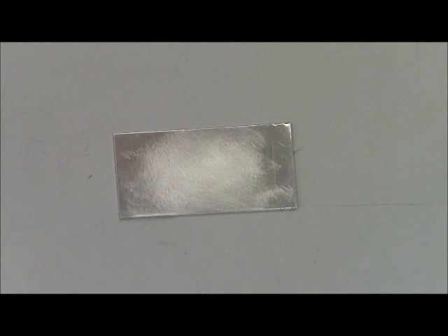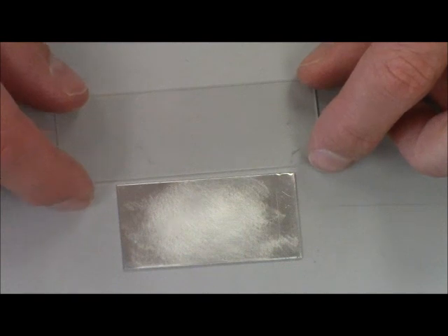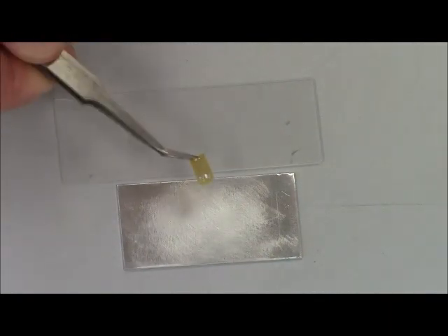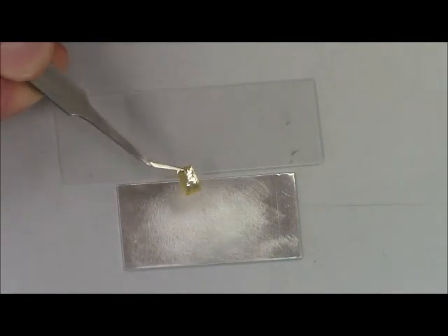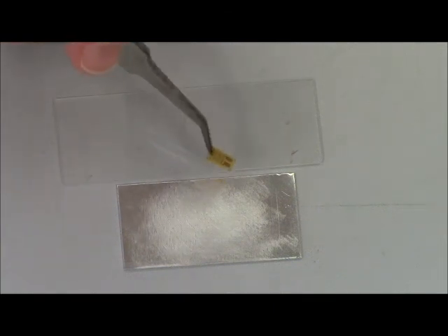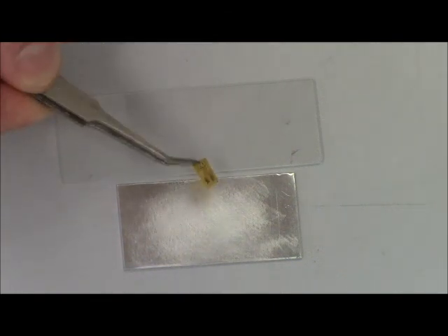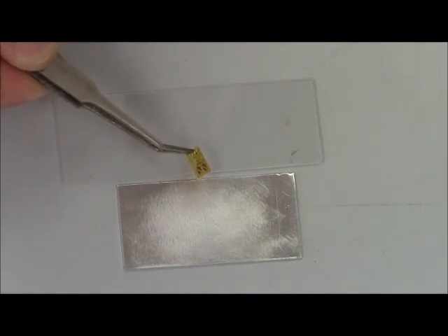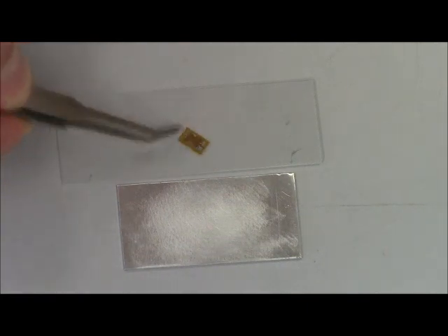In order to handle the strain gauge, I'm going to take a glass slide. And again, the glass slide is optional. But I'm going to take it, and it's been cleaned with isopropanol. Using a pair of tweezers, I'm picking up one of the practice strain gauges. You'll notice there's a shiny side and a dull side. The shiny side would be the side with the active gauge and the pads that can be soldered to. So we want to make sure that that side is up. Placing that on my clean glass slide.